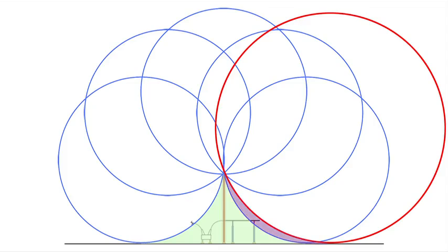So this is that window of stroke currents between this red circle and the stroke currents that cause this blue circle that we're worried about. Anything greater than that red circle, we know it'll be able to strike the mast and everything under here will be protected. Anything less than that blue circle, we understand the insulation will be able to handle, and so we're not really worried about that.